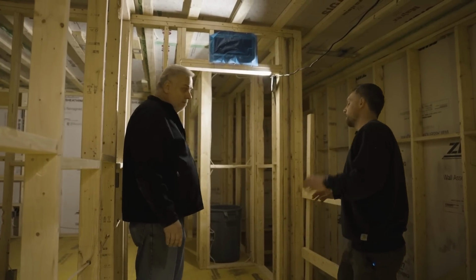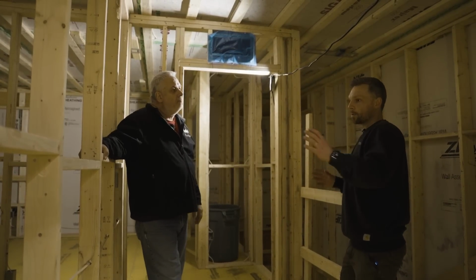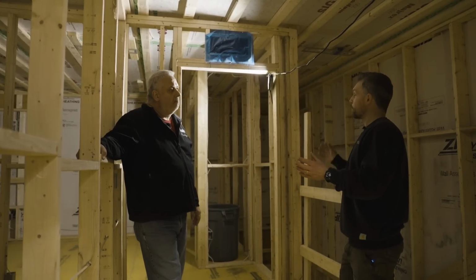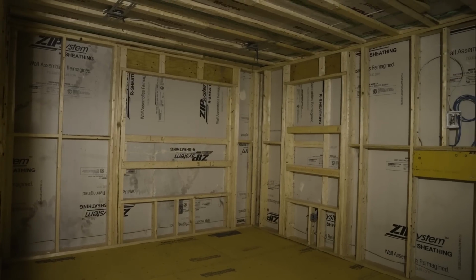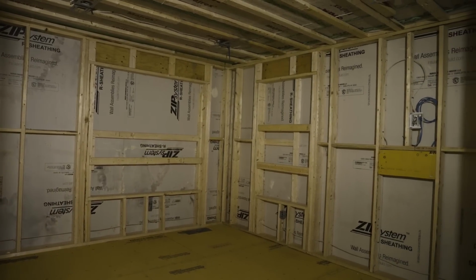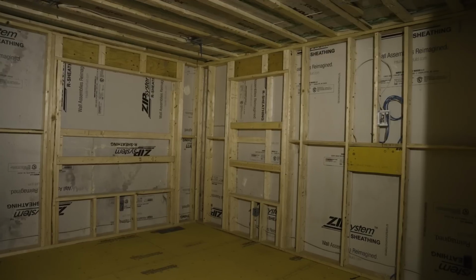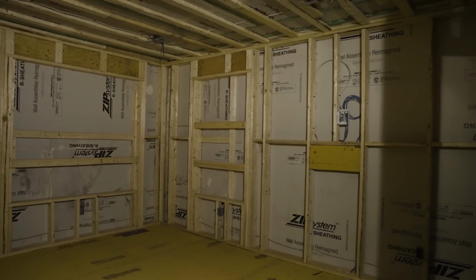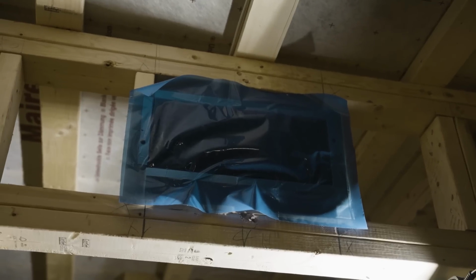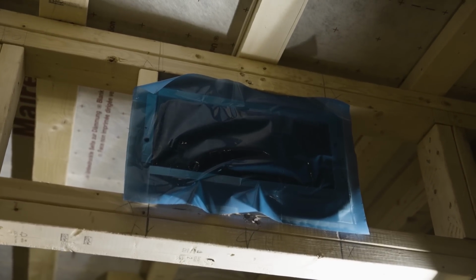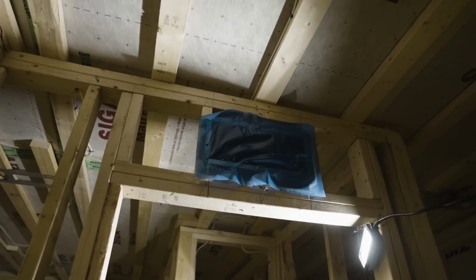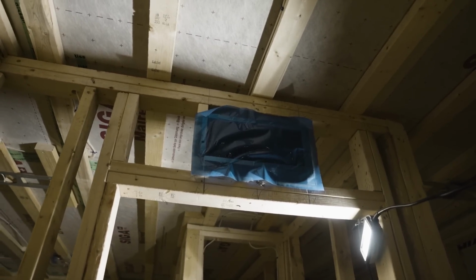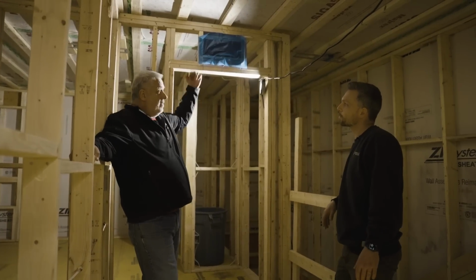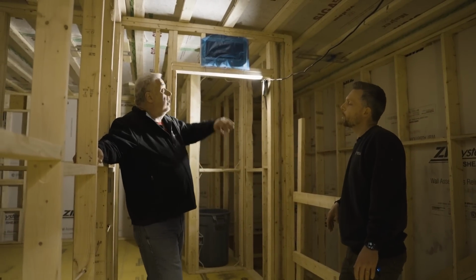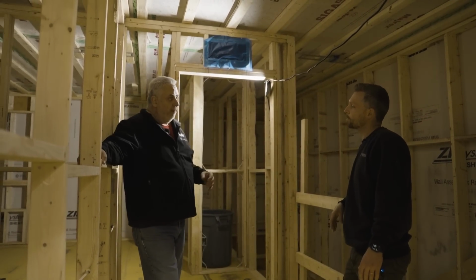It's all based on the load for each bedroom. This bedroom has two exterior walls, two windows, so the load here is going to be more than, say, the load in this other bedroom. So for this one we need more than just the undercut of the door—we needed to provide more open pathway to get back to the return. So when that kicks on, it's basically sucking from the hallway, and the hallway in turn sucks from the bedroom.